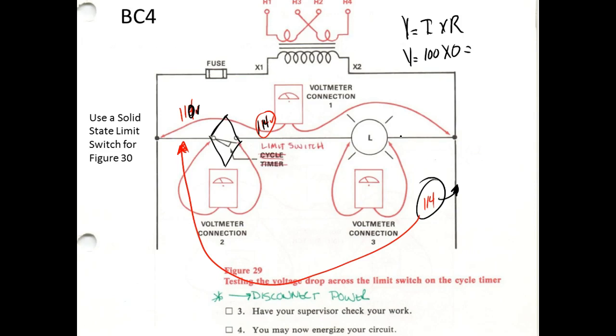You understand? So this is going to be the big difference you should notice between the solid state relay - you're going to measure something different between the coil and L2, L1 on the limit switch. On the limit switch, whatever you measure on the coil will be what you measure over on L1, because a limit switch drops no voltage. It's not supposed to drop any voltage. But all your solid state devices are going to do that.